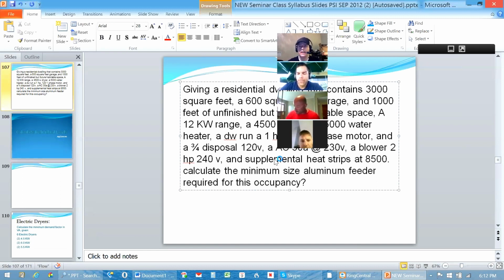The first thing we do in the residential standard method, and it's always going to be standard method unless they tell you specifically otherwise, so that's your default, is take all of your square footage under 220.12 at 3 volt amps per square foot. We include the 3,000 square foot living space. We exclude the 600 square foot garage, but include the additional 1,000 square feet of unfinished space with future applicable use. So we end up with 4,000 total calculated square feet times 3 volt amps. That gives us 12,000.